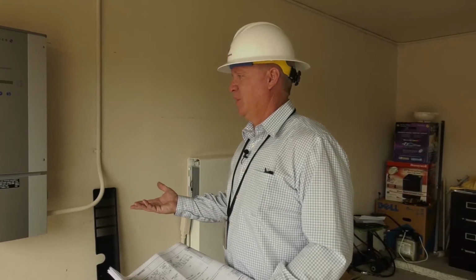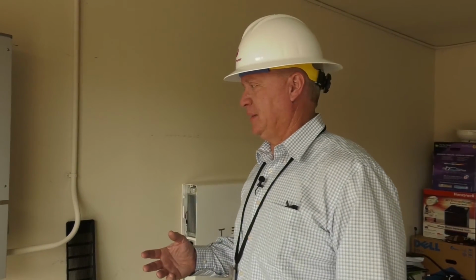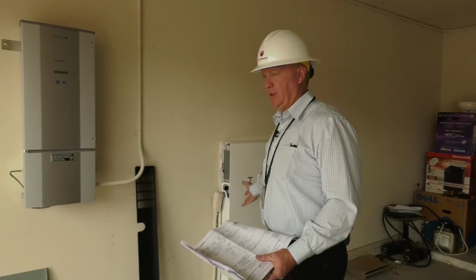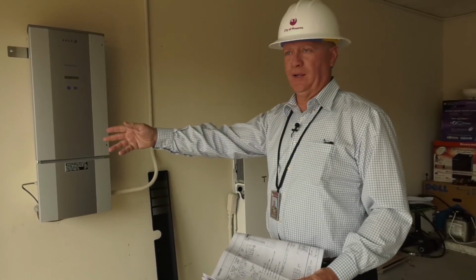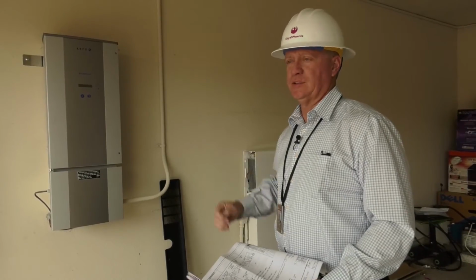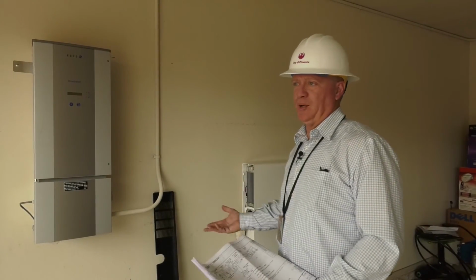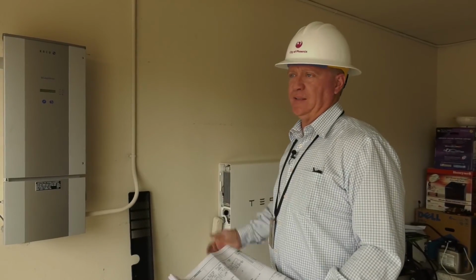Well, by understanding the basics of electricity, wire sizing, breakers or fuses protect the wiring, the circuits. So if you understand the basics, even if you don't understand anything how this works, if you know that it produces 30 amps of current, then you can make sure that the wire and the breakers going to it are sized correctly and can protect the rest of the system.